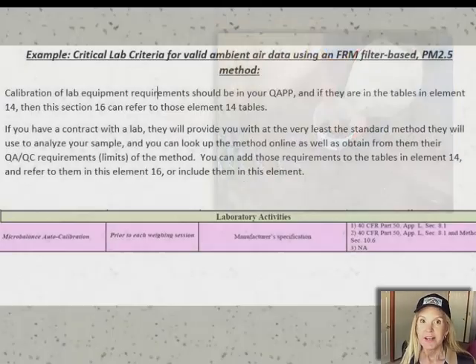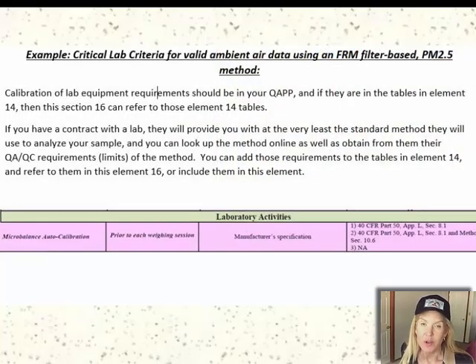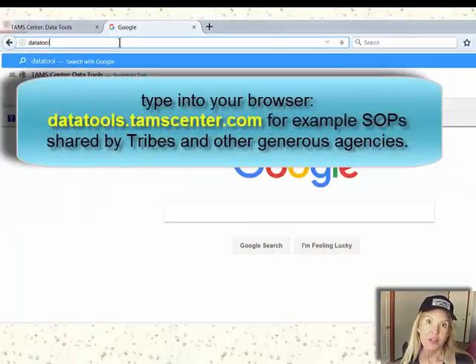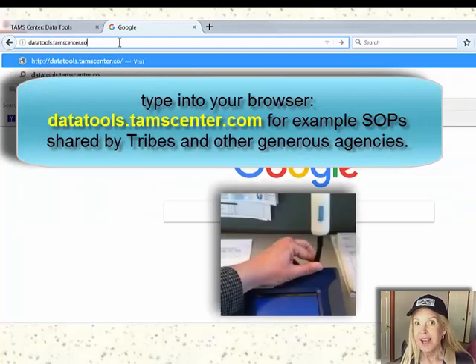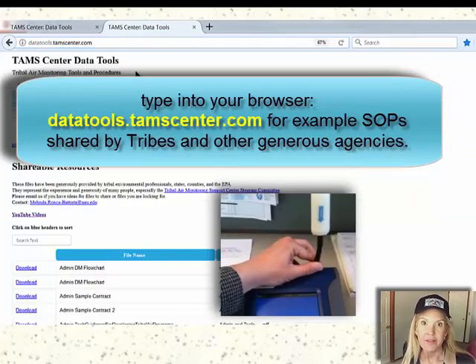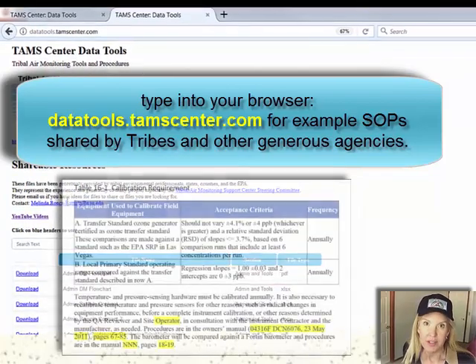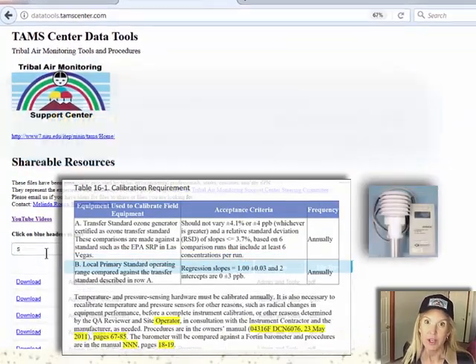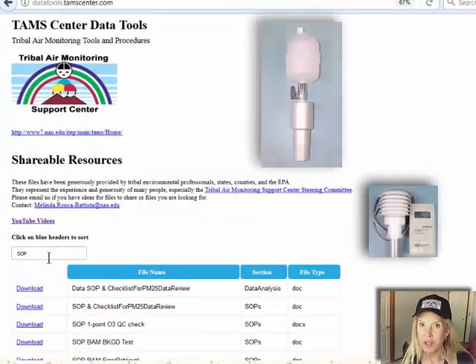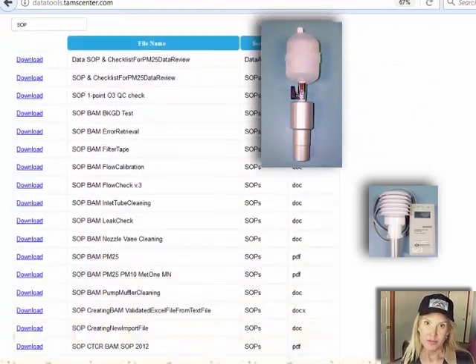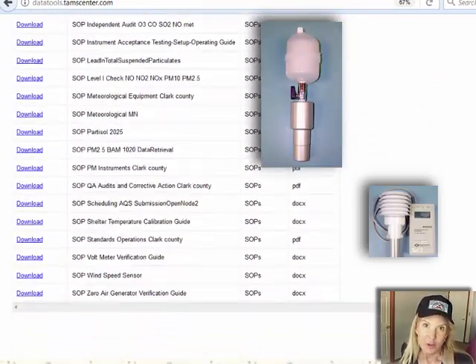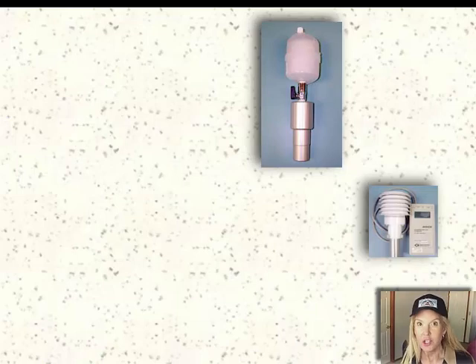Remember, you have to state the requirements in this quality assurance project plan. You should be able to reference SOPs for calibrating any equipment that you use, that you attach, and then this section can have a table that summarizes the requirements for calibrating your field instruments, as well as for calibrating your transfer standards, those handheld instruments that you use to periodically check the performance of your field instruments.